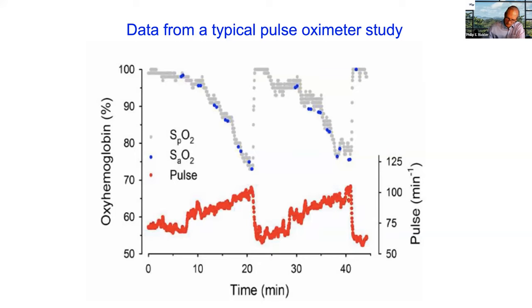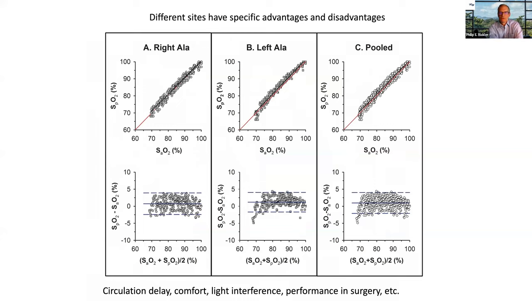So data from a typical pulse oximeter study could look like this, where you can correlate the saturation level measured by the pulse oximetry, or SpO2, versus the arterial blood saturation. For a well-performing device, there's a high correlation between what's measured with the pulse oximeter and what's measured in arterial blood.